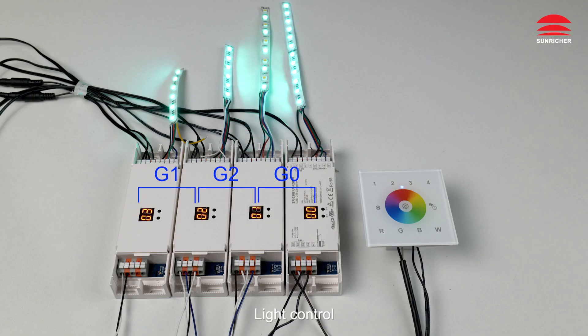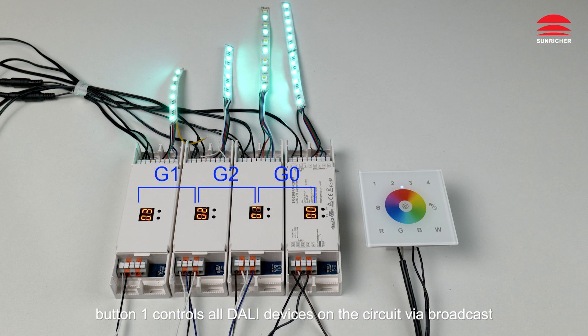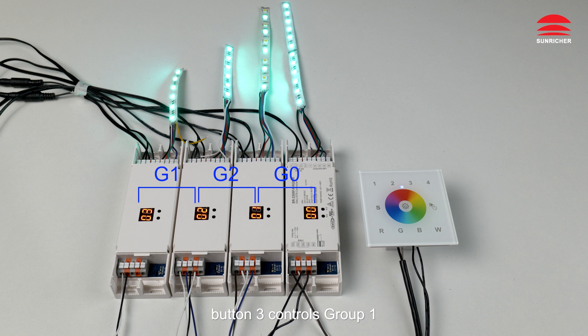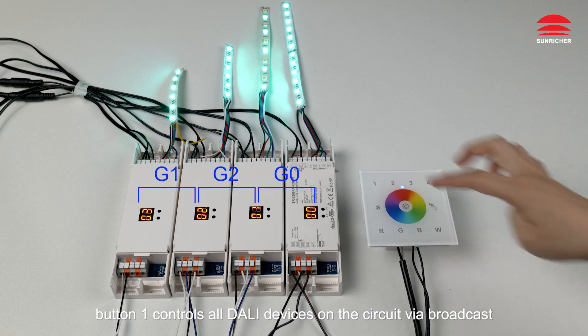Light control: When the rotary switch arrow position is at zero, button one controls all DALI devices on the circuit via broadcast. Button two controls group zero, button three controls group one, button four controls group two. Button one controls all DALI devices on the circuit via broadcast.